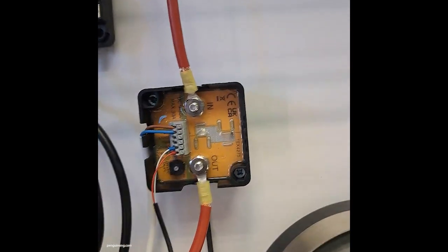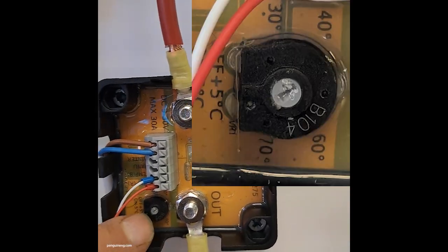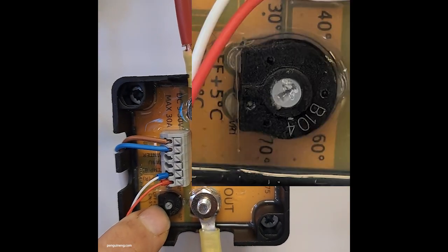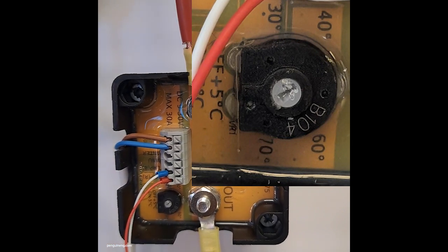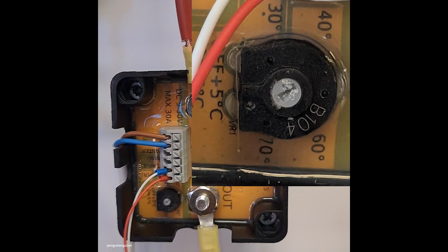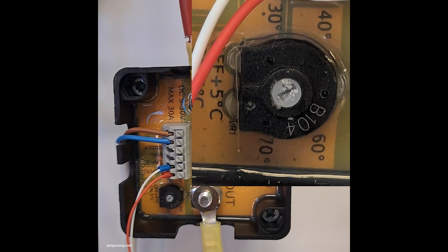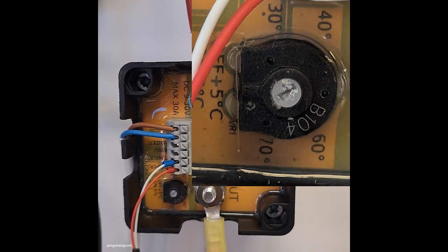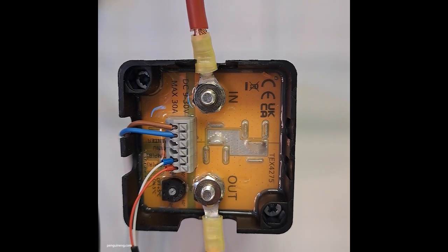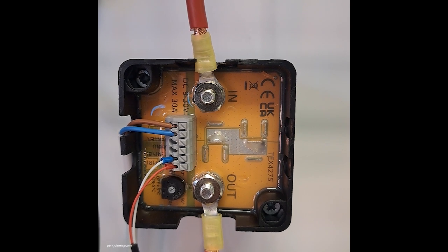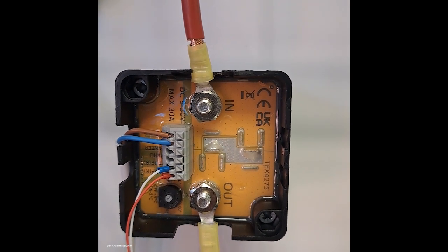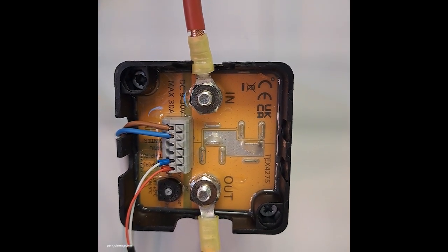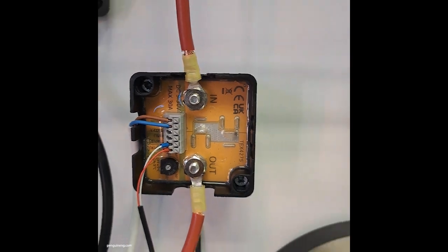On the controller, there is a temperature setting dial that lets you adjust the maximum temperature between 30 and 60 degrees. As well as allowing you to set your preferred temperature, it contains a fail-safe device that will automatically shut the whole system down if the temperature gets above 83 degrees. The hot water is delivered up to the hot water input of the mixer, where you set the temperature by adjusting the handle in the normal way.